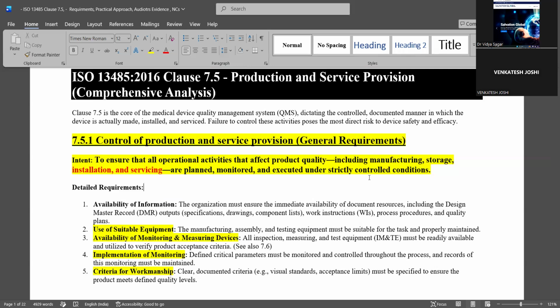It also includes sterilization - which way you are sterilizing, how you have control on the sterilization if you are outsourcing it, and what are the storage conditions. All of this has to be planned, monitored, and executed under control conditions - the whole of clause 7.5. There are about 8 subclauses or sections in 7.5, and everything talks about these same two sentences, just in detail.